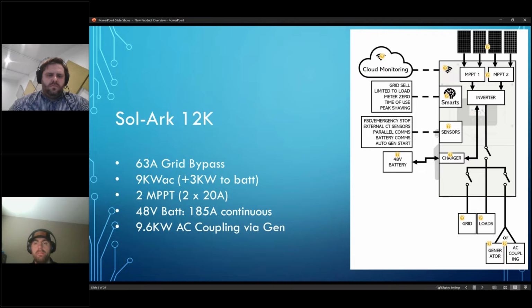So just to break it down — a quick overview of our 12K. It has 63 amps worth of grid bypass built in, with 3 AC breakers in the user area. It puts out 9 kilowatts of AC, and simultaneously 3,000 watts to the battery.